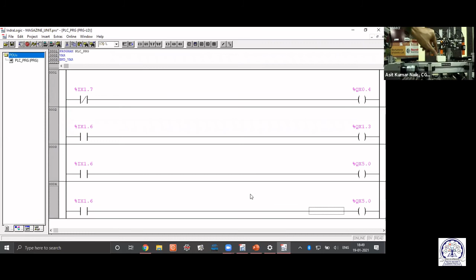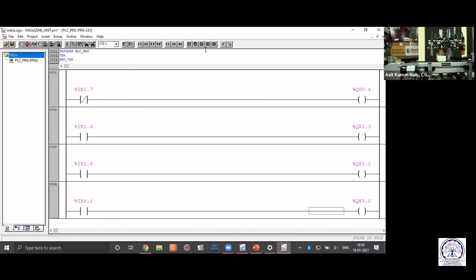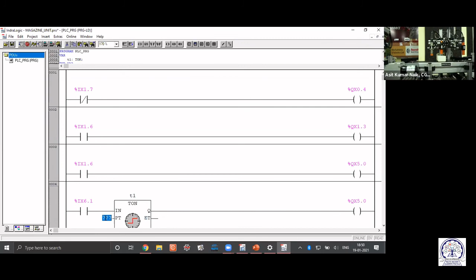Sorry, a relay. You take a normally open contact. Just one minute. After it retracts, you need a reed switch input. The reed switch is connected at serial number 32. You can check. Yes, so that's IX 6.1. Now the cylinder is extended. You need to add a timer, a T off delay. Sorry, T on, my bad. Let it be T on, for 1 second. So one second time delay. Next, after 1 second, it is.